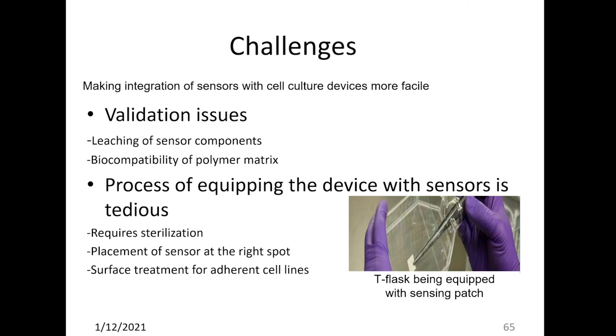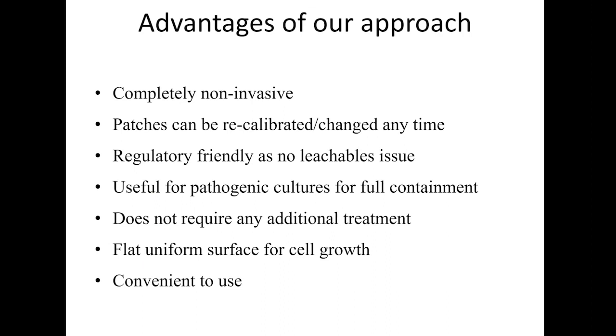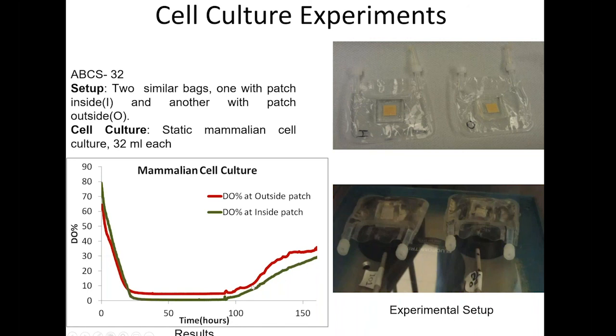There's one more issue. Whenever you're sticking a patch-based sensor in a vessel, there's concerns once you get to the FDA. It's not an issue for R&D, but if you're going into something that's going to go into someone, FDA will want to know all about the leachables, extractables, and then positioning the sensor. So we came up with this new concept where what if we just make a diffusible surface in the bioreactor, and then you can put the patch right outside a gas permeable wall. It becomes completely non-invasive. Patches can be recalibrated. It's very friendly to regulators. You have full containment. So we took these ViewLife bags and we actually mounted a patch outside the bag. And because we had to do the validation, we also put a patch inside the bag and pretty much get the same results. There's a slight lag because of the diffusion, but the cell culture results are more or less identical. So we now have literally outside the box technology.